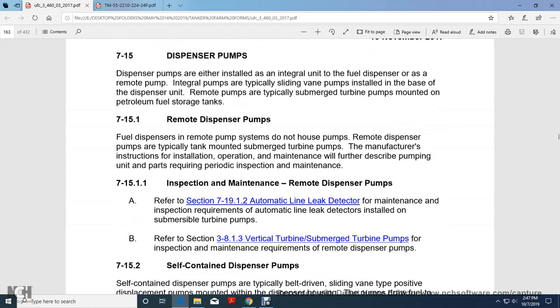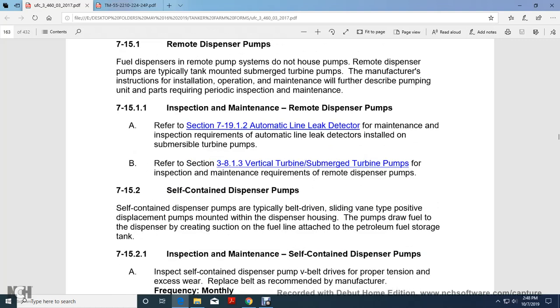Alright, dispenser pumps. Dispenser pumps are either installed as an integral unit with a fuel dispenser or as a remote pump. The integral pumps are typically sliding vane pumps installed in the base of the dispenser unit. Remote pumps are typically submerged turbine pumps mounted on the petroleum fuel storage tanks. Remote dispenser fuel systems do not house pumps in the dispenser. Manufacturer's instructions for installation, operation, and maintenance will further describe pumping units and parts requiring periodic inspection and maintenance.